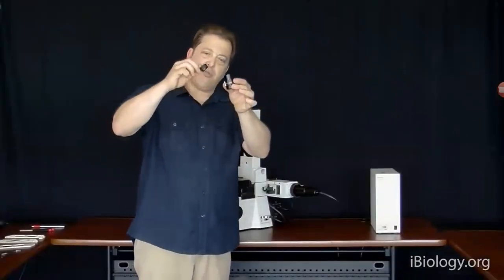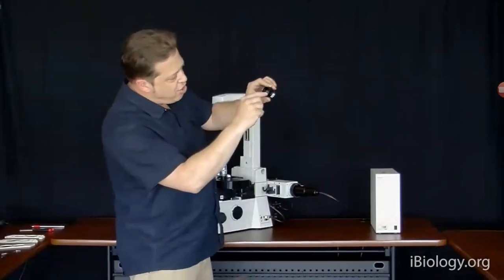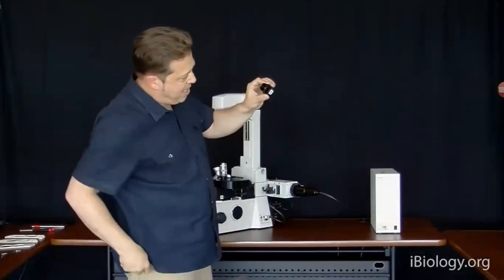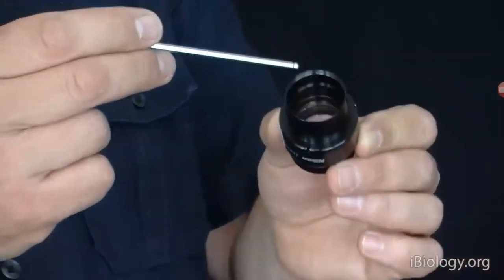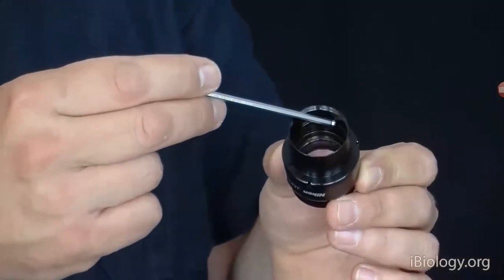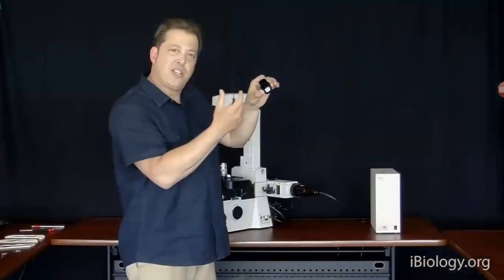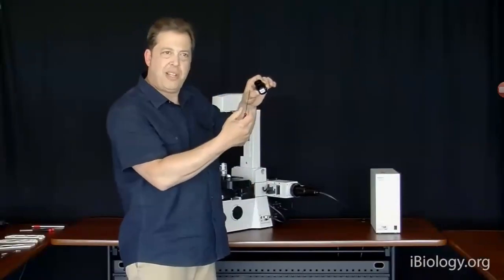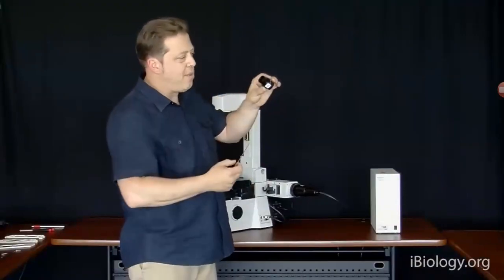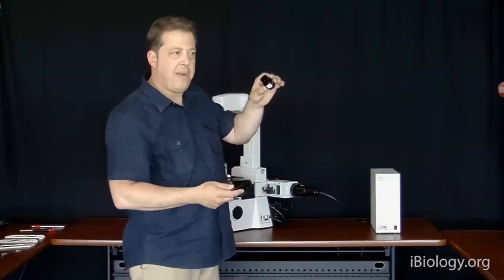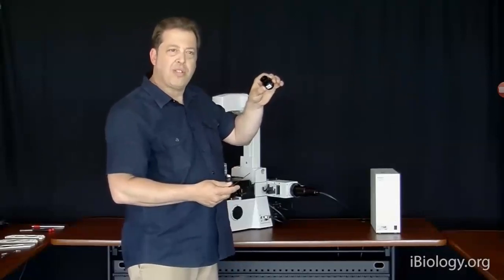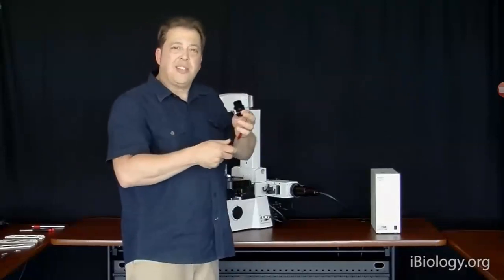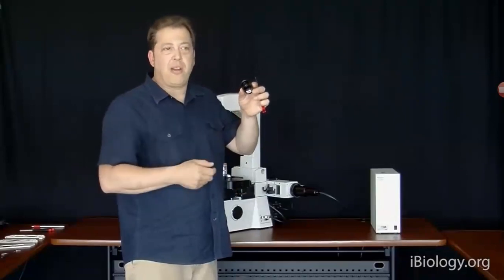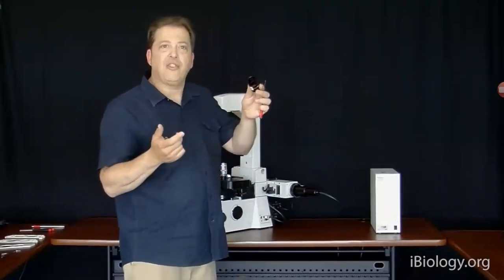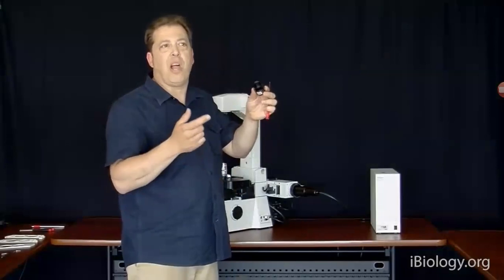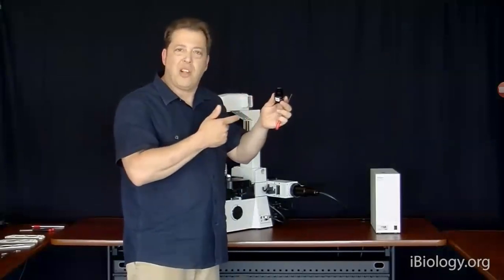And you can see I just unscrewed this little ring, and there's a little shelf inside this eyepiece. And that shelf is where we would put what's called an eyepiece reticle, which is basically a small scale bar that's printed on a piece of glass that we would be able to put onto the eyepiece of the microscope. It's a nice accessible image plane in the microscope, and it's a good location if you wanted, for example, to block certain wavelengths of light.